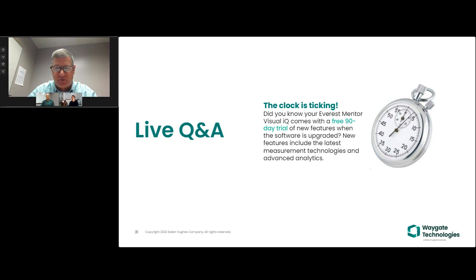Are the cursors placed where they should be placed? And a lot of manipulation, really the point there is for you to be able to study that measurement. And when you make an answer, whether it's in or out of limits as an example, you're confident in that because you've got these tools that can help you do that. So that's really what real 3D measurement means.